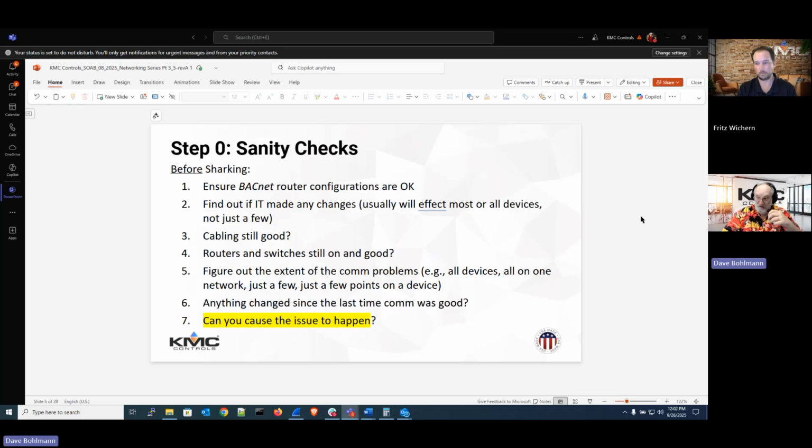In the previous sessions we talked about what kinds of things you are looking for and what can cause those things. A lot of times the complaint is that the network's just too slow, meaning you're using Converge or Connect or Total Control or Commander or some operating workstation, and the communication's just slow. It does not get the points quickly enough, and therefore maybe not all the points are coming in.